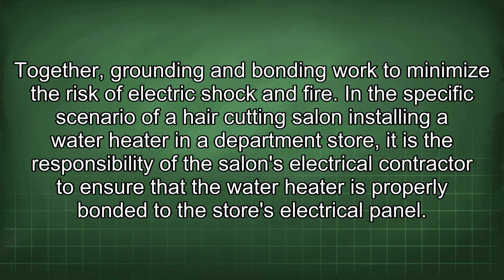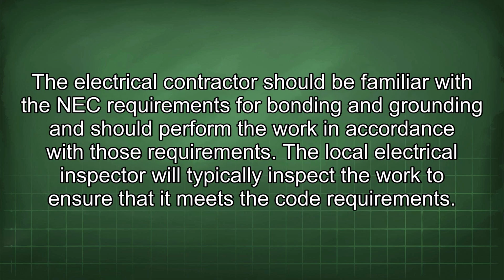In the specific scenario of a haircutting salon installing a water heater in a department store, it is the responsibility of the salon's electrical contractor to ensure that the water heater is properly bonded to the store's electrical panel. The electrical contractor should be familiar with the NEC requirements for bonding and grounding and should perform the work in accordance with those requirements.